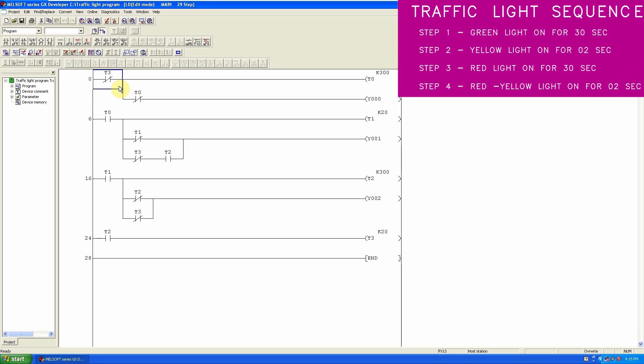This normal close contact of timer T3 will start timer T0. The set point for timer T0 is 30 seconds. We use the normal close contact of T0 to turn on the green light Y0. When the 30-second timer is over, it will open the normal close contact T0 and turn off the green light Y0. The first step programming is completed here.